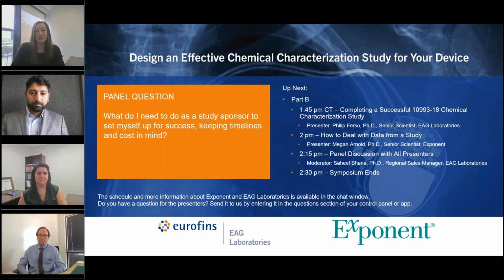I'll chime in from the tox side since we're always the ones waiting on the data. Most of the time, this is the last part or one of the last parts of a biocompatibility evaluation. I always encourage study sponsors and our clients to get started on chemical characterization as soon as you can, because things happen and it can take longer. You may have some compounds that are concerning that fail a risk assessment, and then you're stuck.